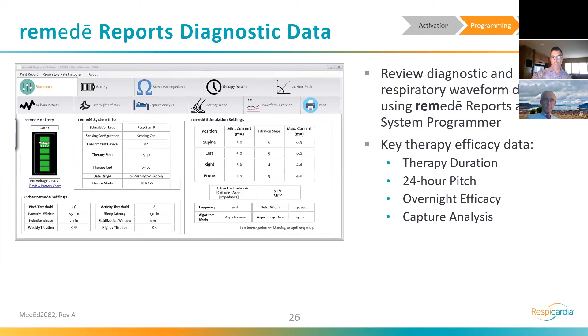The first of those is the therapy duration trend, and this really is giving us a nightly data point of the durations of therapy being delivered each night. The maximum amount of therapy delivered is of course set by the start and stop times that we have selected for this patient. And most commonly, we're not delivering the absolute maximum. The therapy will suspend as patients change sleeping postures. It will suspend as they sit up and get out of bed if they're using the restroom in the middle of the night. But also, we can see less than maximal durations just on the daily schedule.